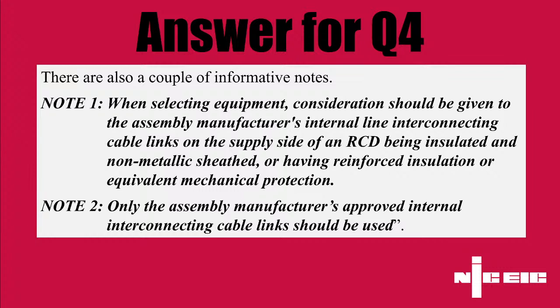You're right. Yeah, section 419, Jake, is for those particular instances where, because of your location or because of the high current rating and the low ZS to achieve, or a combination of the two, there's no way that you can achieve the maximum ZS of that overcurrent protective device at the origin. In those instances, what you have to do is, in the intake room, apply equipotential bonding to all of the accessible conductive and extraneous and exposed conductive parts within that area, to ensure that your overcurrent protective device will eventually operate under fault conditions. It just won't operate quickly enough to achieve the disconnection time, because you can't achieve the ZS.